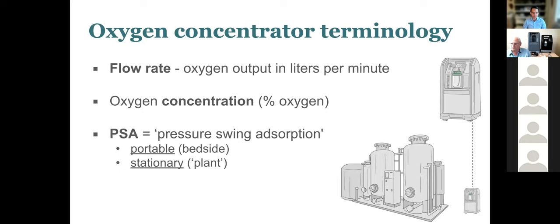There are a couple of different variations of this, but this is the most common that we would be throwing around. There are two different types of oxygen generator, generally speaking, that we're going to be referencing here. Portable or bedside oxygen concentrators, which function by using pressure swing adsorption, and we'll talk about that in a sec. And then there's stationary, and these are often referred to as oxygen generating plants. The oxygen generating plant is the larger image on the bottom left, and the portable or bedside concentrator is what we see on the top right and, for scale, at the bottom right.